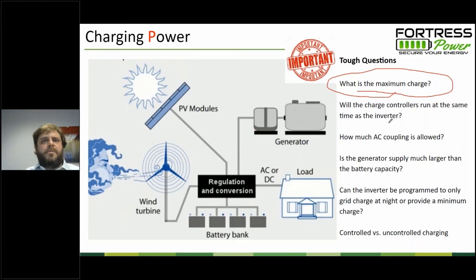So in the off-grid setting where you have very large battery banks, you're not too concerned about having lots of charge controllers and lots of inverters because you also have lots of batteries. It's when you get into a smaller, shorter duration battery that might only back up a whole house for a couple hours that you have to start looking at, okay, if I'm doing charge controller charging with a solar array, AC charging with a solar array, and grid charging with a grid-tied battery inverter, what is the cumulative effect of all the charges happening at once? And you could say, well, I want to charge either from my charge controllers or from my battery inverter. But the question is, do you have it programmed to prevent the 2 resources from contradicting each other?